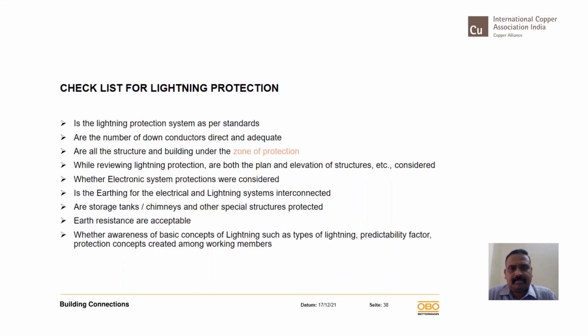Secondly, the number of down conductors, whether they are direct and adequate, is important. You need to ensure all the structures and buildings are under the zone of protection, which means in a clustered area of multiple buildings, there may be several buildings located here and there. For every building you need to do the risk assessment and then ensure what type of lightning protection is required there, and that needs to be calculated based on the zone of protection. And while we review the lightning protection drawing, you'll have to ensure both plan and elevation are seen, to ensure the routing conditions, the feasibility of routing the conductor, whether it is practically viable or not.